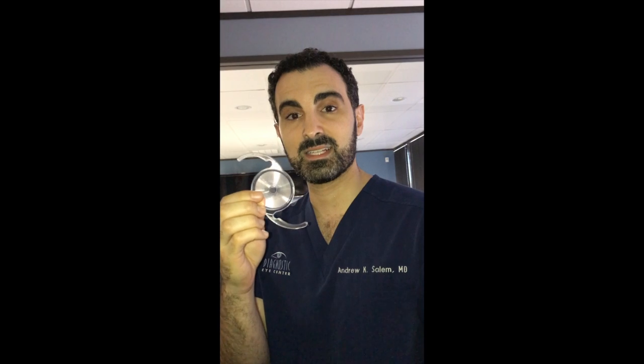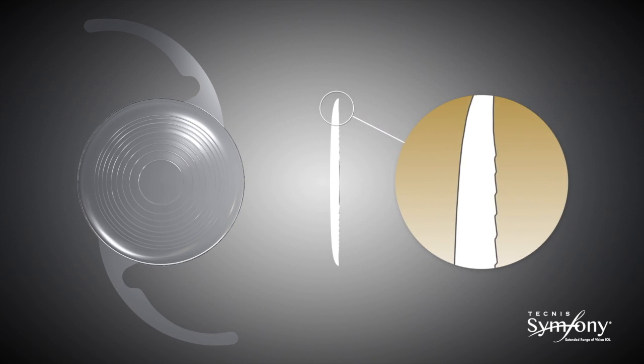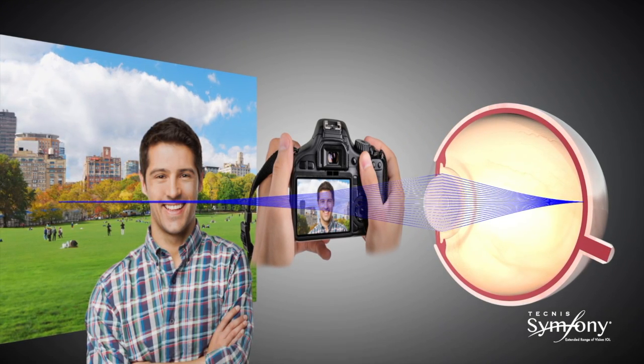In this case, this Tecnis Symfony intraocular lens. What this lens does is allow for a continuous range of vision from distance all the way to arm's length and sometimes closer, effectively reducing your dependence on contacts and glasses. The new Symfony lens has a unique design — the lens has what are called echelettes, or small grooves on the back surface of the lens, placed in just the right way so that light focuses over a large range of distance instead of just a single point.